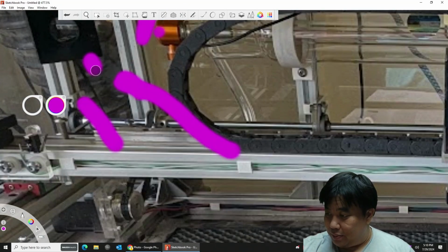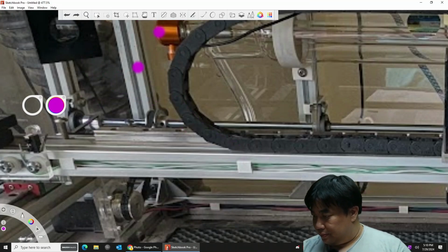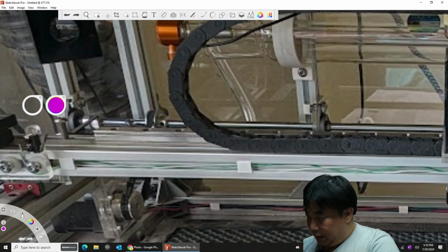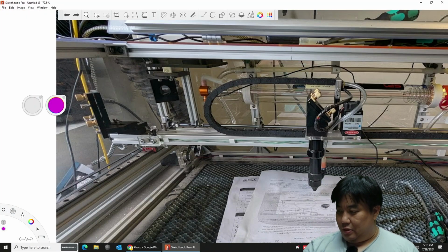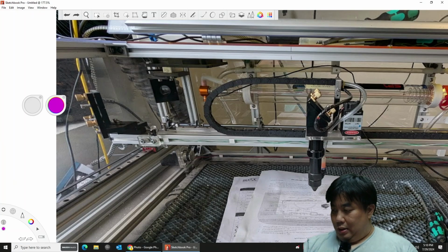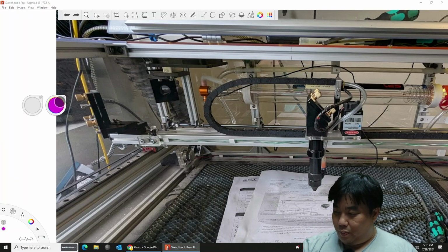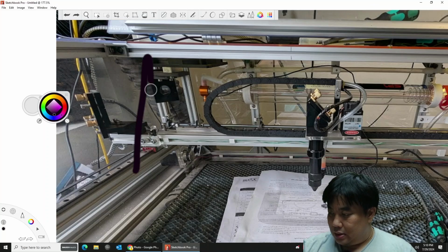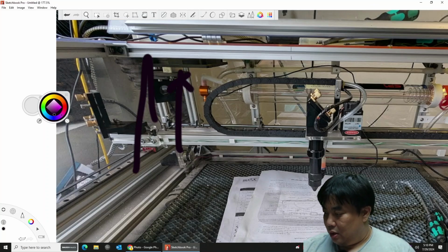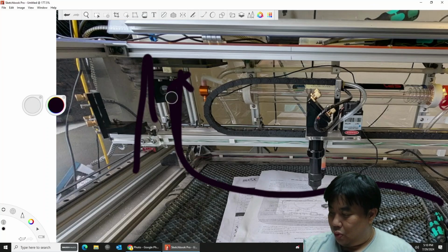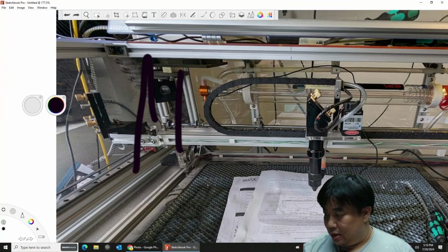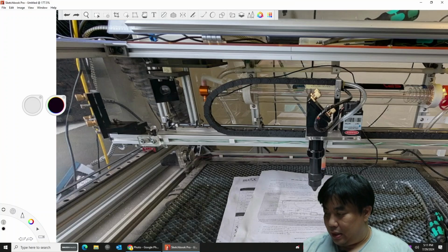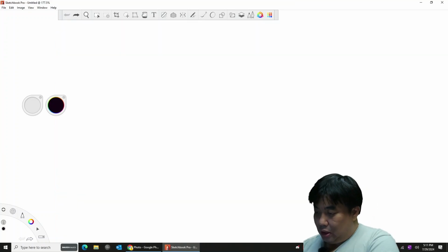you may not be able to see it, but there's a little bit of debris or haze on the mirror. And that's basically indicating that the lens has already been fouled a little bit. It doesn't help that this is right by the exhaust gas port, right? So all the air that's coming in is being pulled up with all the dust and debris, and it's being pulled past the exhaust, past the first mirror here, into the exhaust port. Oops, excuse me.